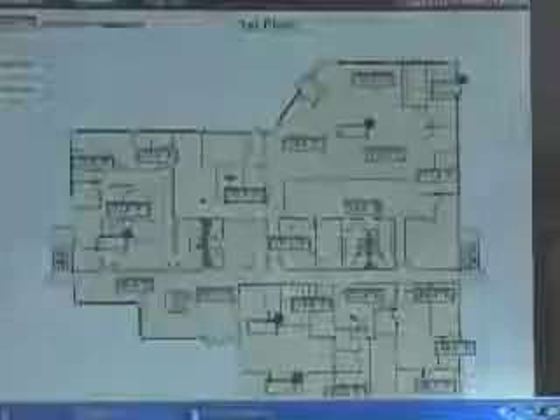The mechanical contractors are on site today working on some of the VAV boxes, replacing electric heat elements. Some of these are fan-powered boxes, and some of the fans are burnt out, so they're fixing those too. We noticed this during the installation process. So if a few are offline and we get some alarms, it's likely just because they're down there working on them.